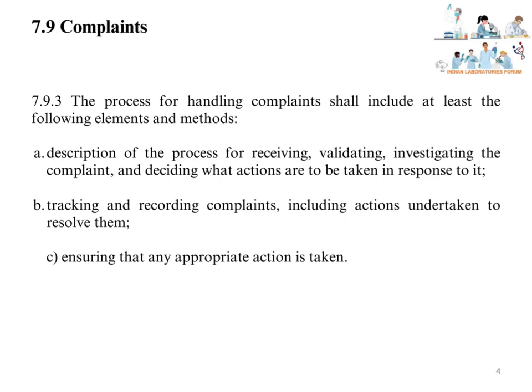The complaint handling procedure should detail the process for receiving, validating or confirming complaints, performing investigations, and deciding on actions to initiate and implement to resolve and avoid recurrence of similar complaints. This also includes tracking and recording complaints including actions undertaken to resolve them, and ensuring that any appropriate action is taken.